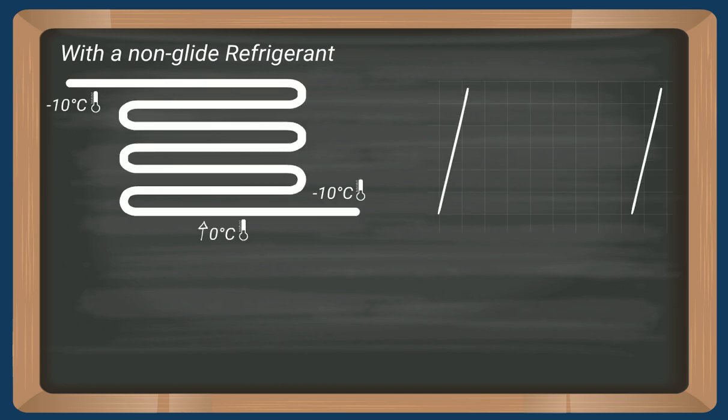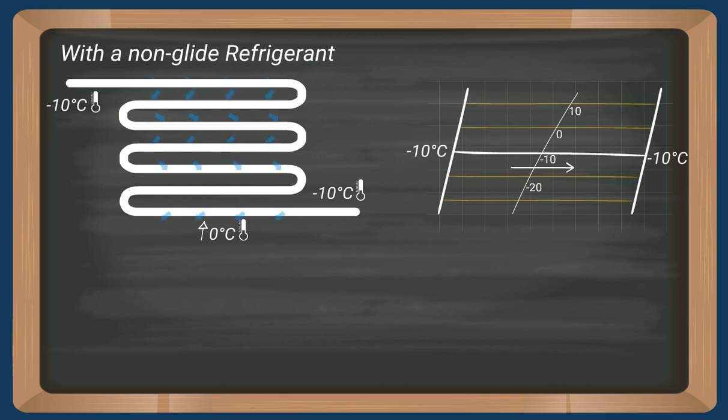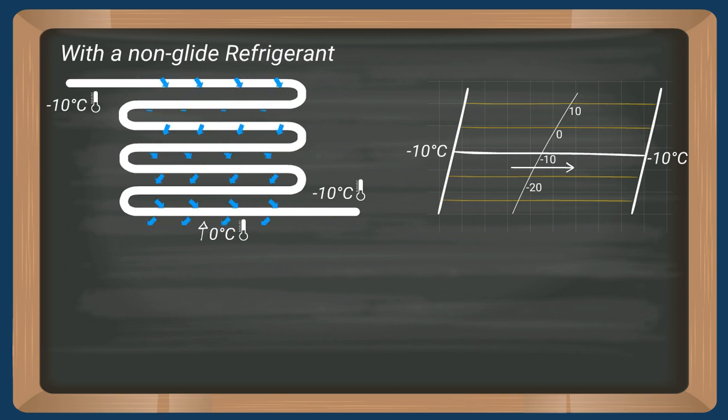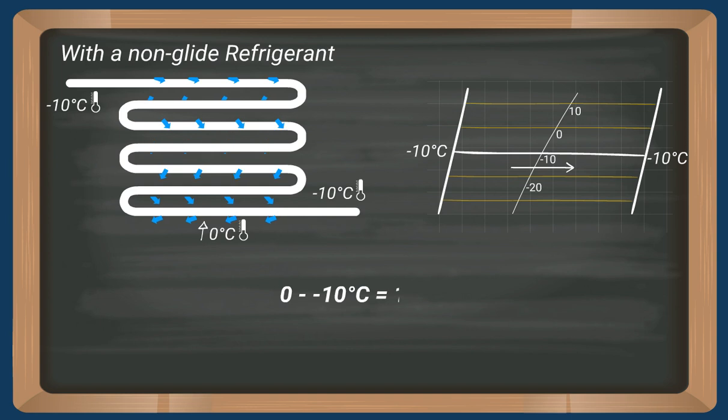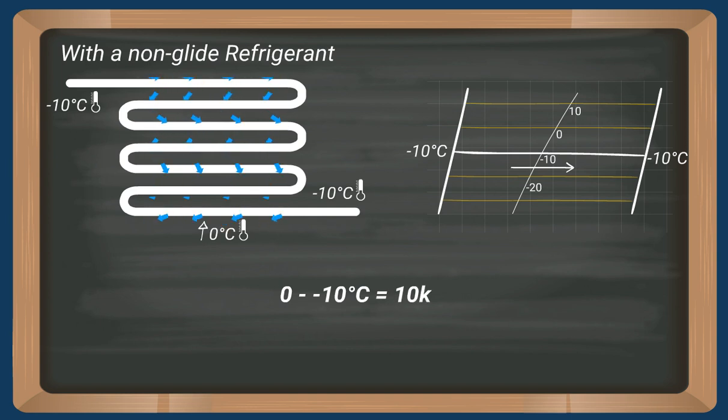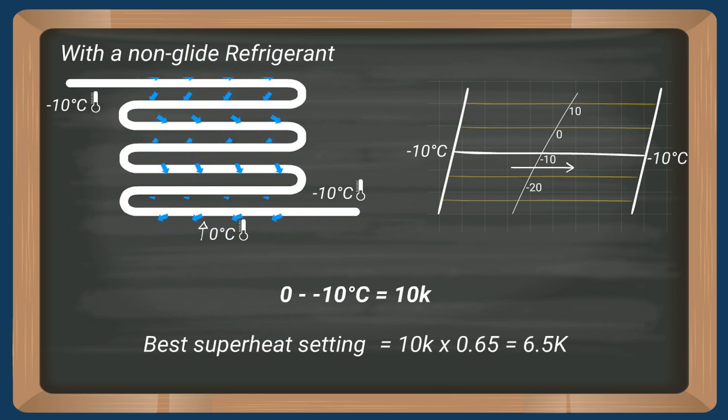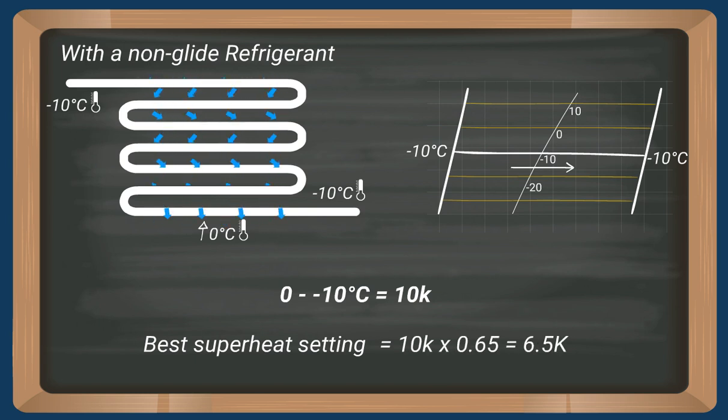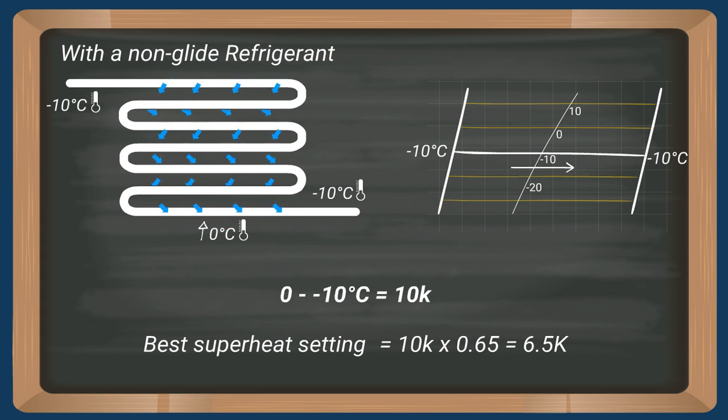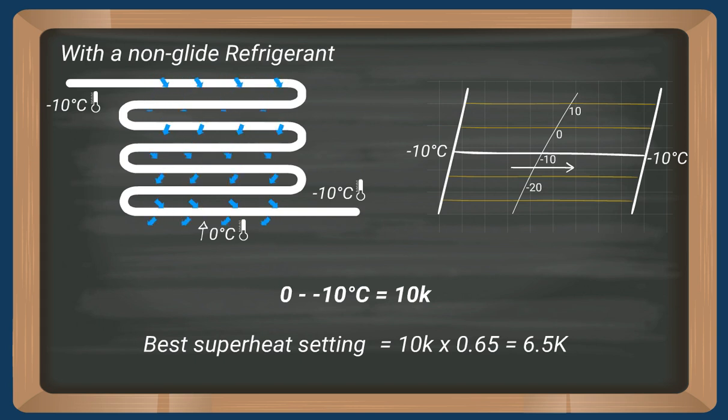Let's first have a look at a normal linear non-glide azeotropic refrigerant. The optimal superheat is, according to EN 328, the temperature difference times 0.65. In this case, it's 6.5 Kelvin.